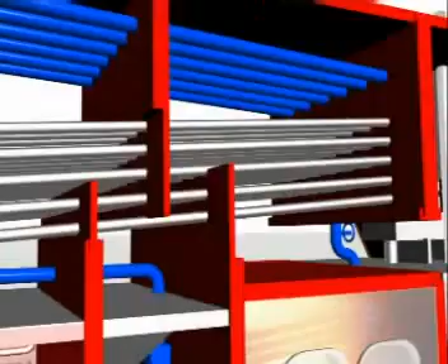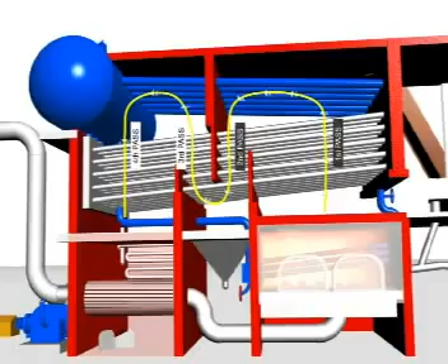Heat transfer. The furnace in-bed cooling tubes transfer radiant heat of the FBC furnace bed, and at the same time these tubes control the furnace temperature to avoid clinker formation. That is why these tubes are called cooling tubes. Hot flue gas from the FBC furnace moves from radiant zone to the convective zone. It passes over the bank tubes for first, second, third and fourth passes and goes out to waste heat recovery unit, which is air preheater and economizer.